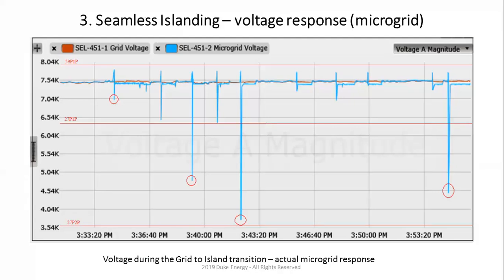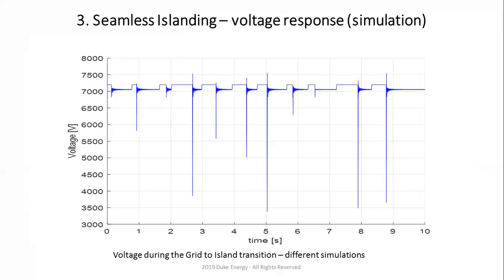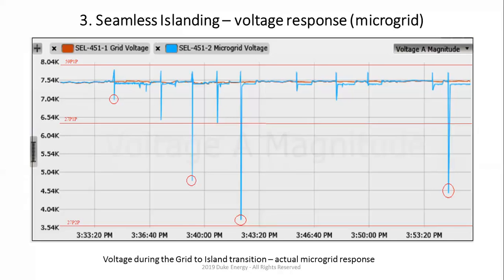I'm sure a lot of you are familiar with the C37.118 synchrophasor data, right? What you have seen over here is simulation. What you see over here is just a part that shows the actual response from the field: voltage sags. This is 27, right? Now, mind you, this is not to detect the islanding. We have detected islanding. We have gone into the islanding mode. This is strictly from the energization of the transformer. You can see 27P1P, the red line, is our first level of undervoltage pickup, and then 27P2P is the second level. These are typical settings within the relays, which now have to understand: is this a transient or is this an actual fault, right?